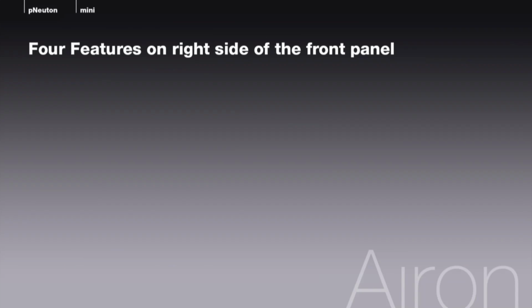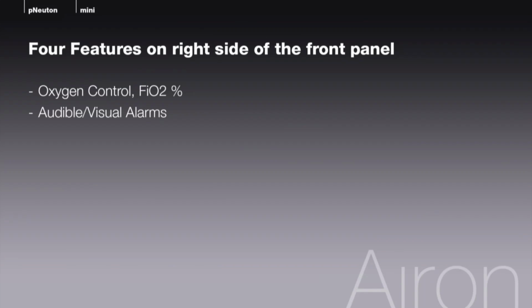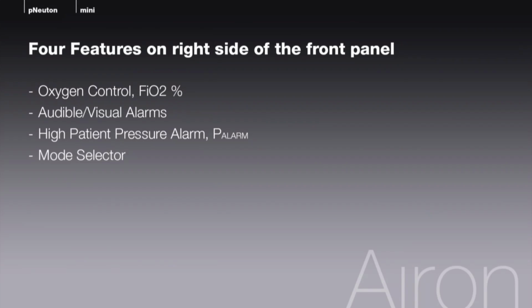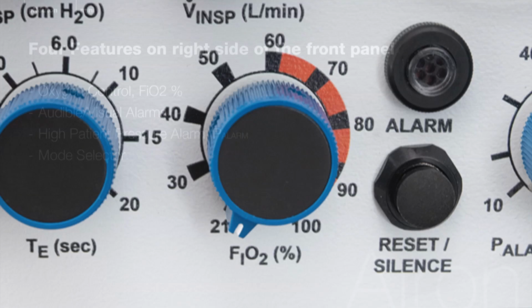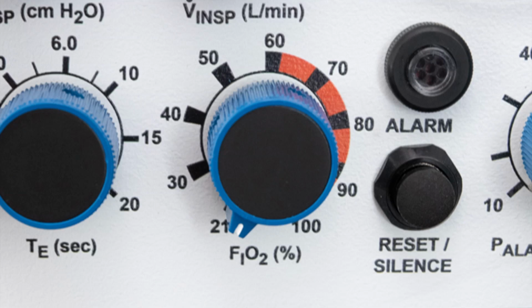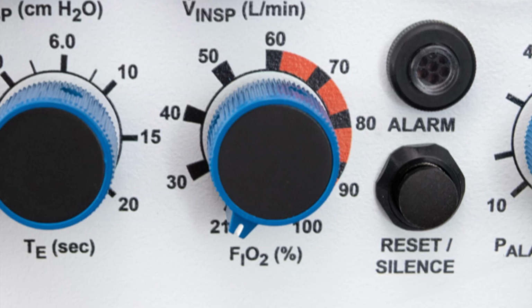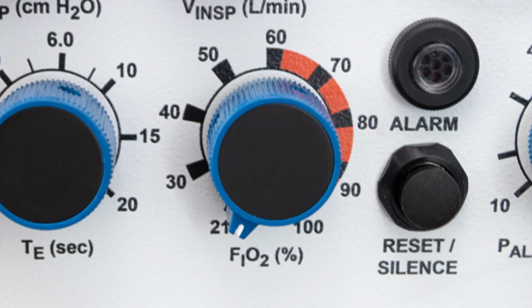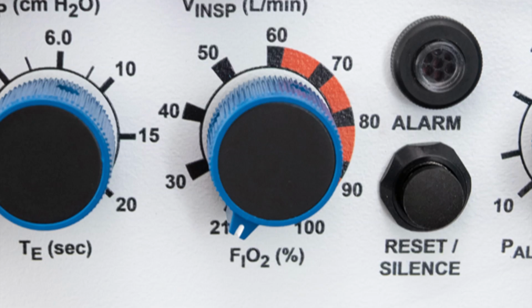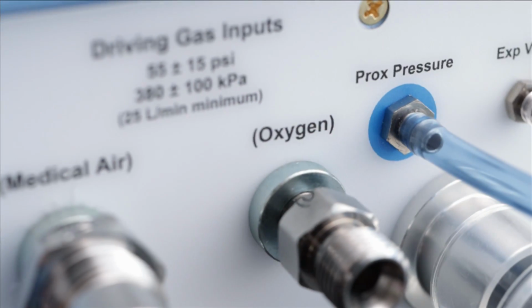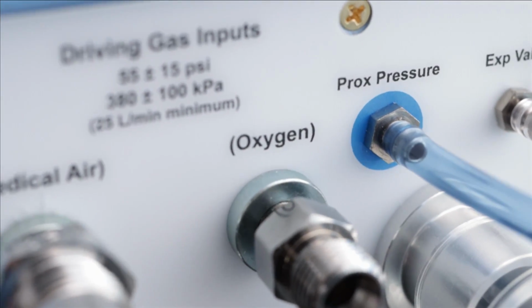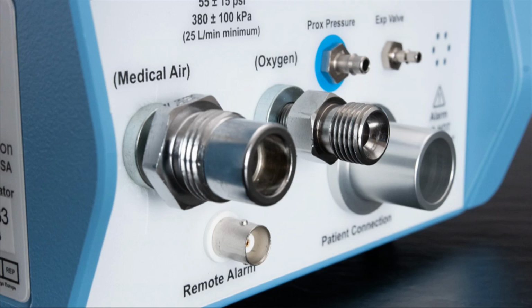Next, let's move to the right-hand side of the front panel to discuss oxygen control, FiO2%, audible visual alarms, high patient pressure alarm, P alarm, and the mode selector. Oxygen control. The pNeuton mini ventilator uses a sophisticated oxygen blender to mix oxygen and air for delivery to the patient. This blender requires both compressed oxygen and medical-grade air for proper operation.